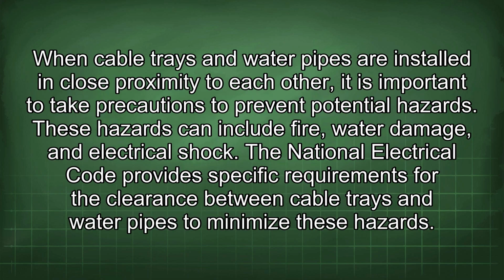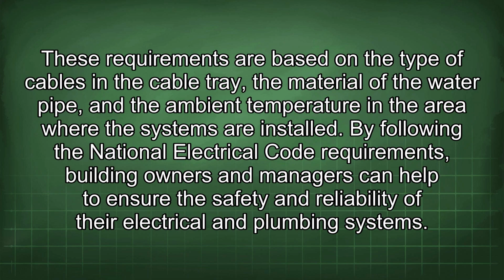When cable trays and water pipes are installed in close proximity to each other, it is important to take precautions to prevent potential hazards. These hazards can include fire, water damage, and electrical shock. The National Electrical Code provides specific requirements for the clearance between cable trays and water pipes to minimize these hazards. These requirements are based on the type of cables in the cable tray, the material of the water pipe, and the ambient temperature in the area where the systems are installed.